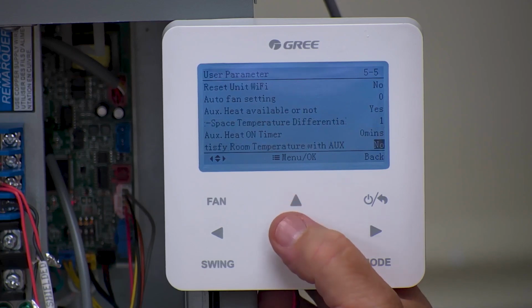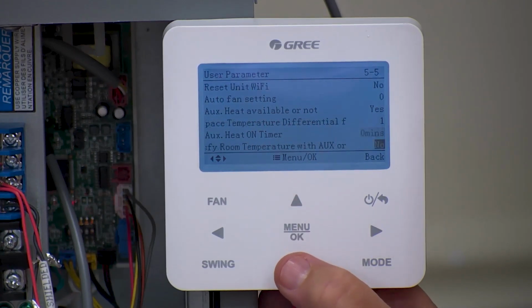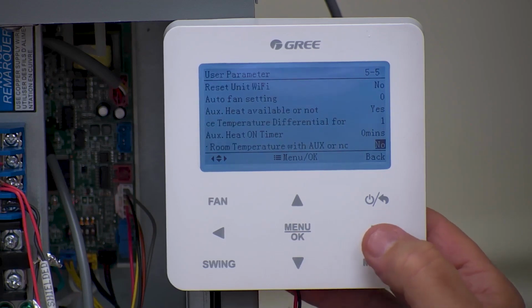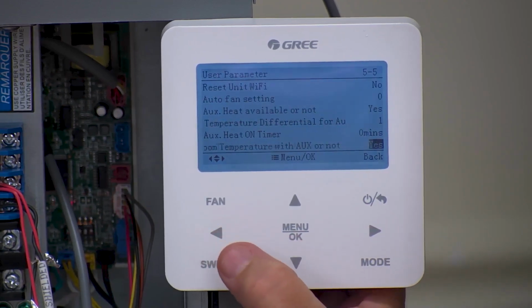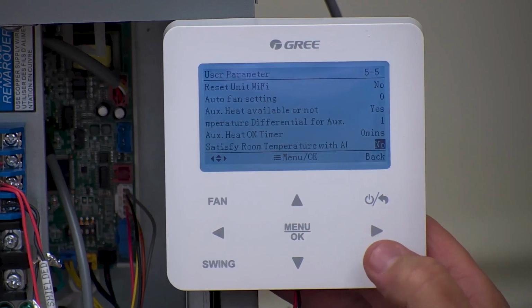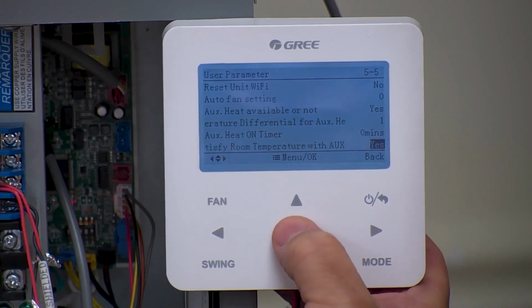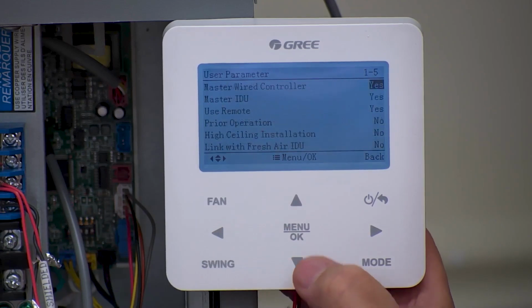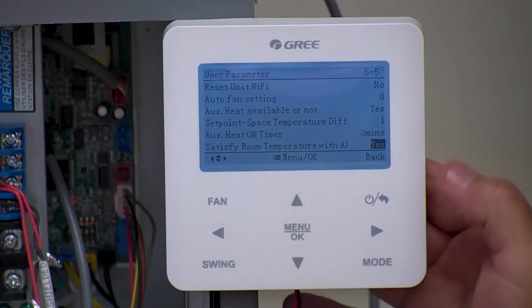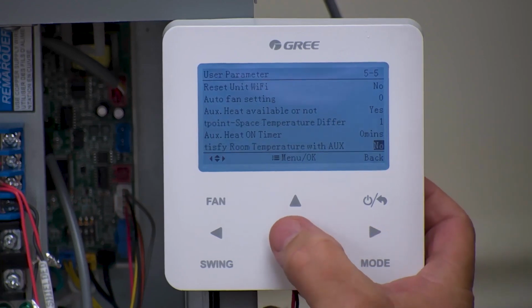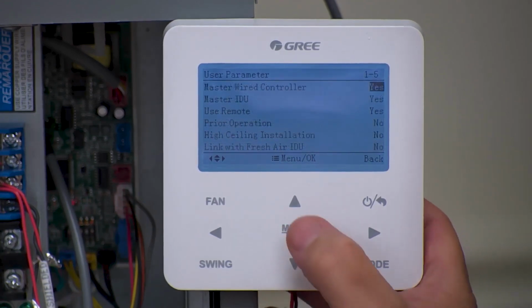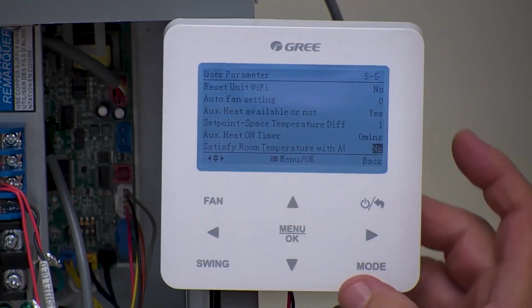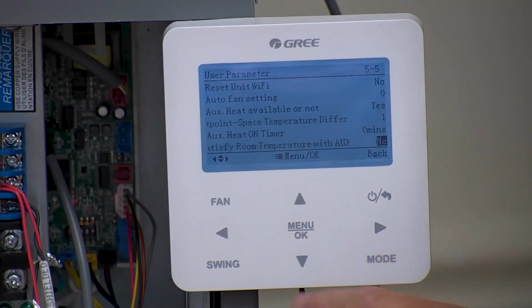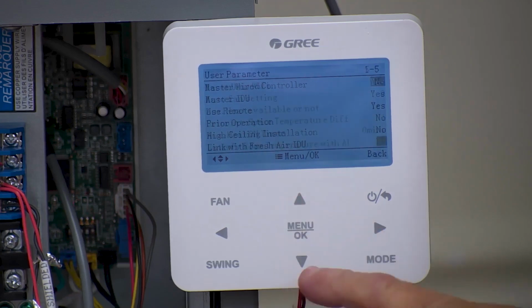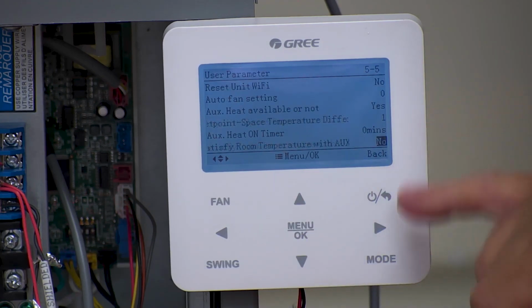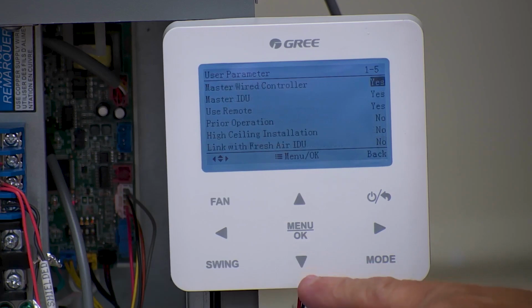We also have the satisfy room temperature with auxiliary heat. Again, I already kind of talked about that. You can set this to yes or no. Just remember when you change the setting, after you change it, once I set it to yes, I have to hit menu. And then if I go back to it, it still says yes. If I go to no, and then I save it, and then I go away from it and go back to it, it should still say no, and it does. Okay, so you've got to save it after you set it, just so you know. So there's your 3 settings you've got to set. That's all there is to it.